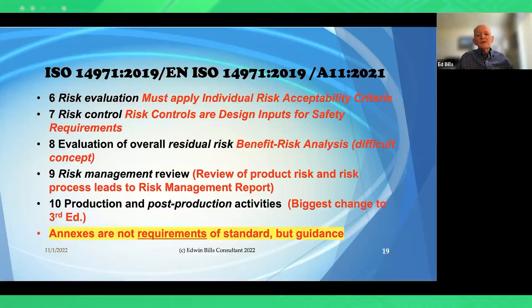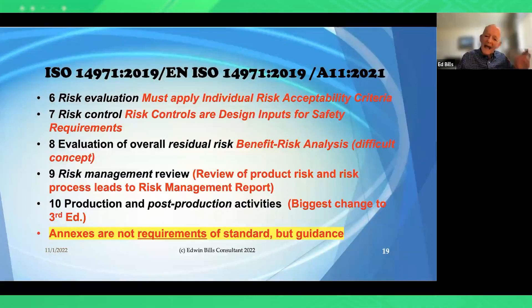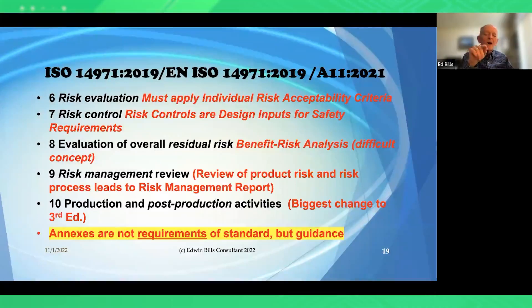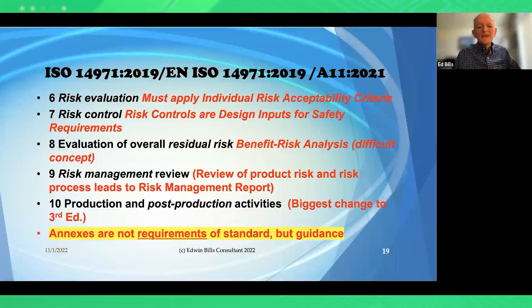During risk evaluation, you must apply individual risk acceptability criteria, which need to appear in your risk management plan. Risk controls are design inputs for safety requirements — this is where the requirement from ISO 13485 comes from. When you develop a risk control, it becomes a design input and the safety requirement for your product.